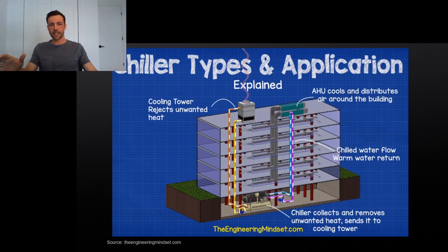When we look at the HVAC system for a building, the chiller is generally located in the basement. The chilled water leaves the chiller on the right side - you can see my mouse, the circuit on the right is going to leave with cool water. The chilled water is going to go all the way to all the floors of the building and cool the air, and also attract or remove the excess heat from the air and bring it back down to the chiller.